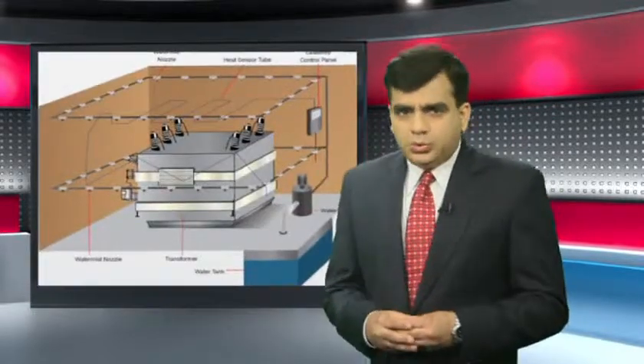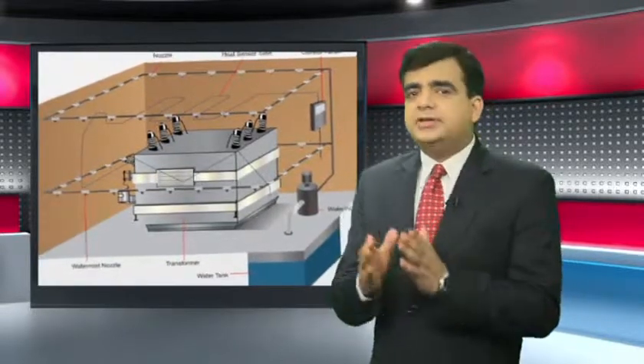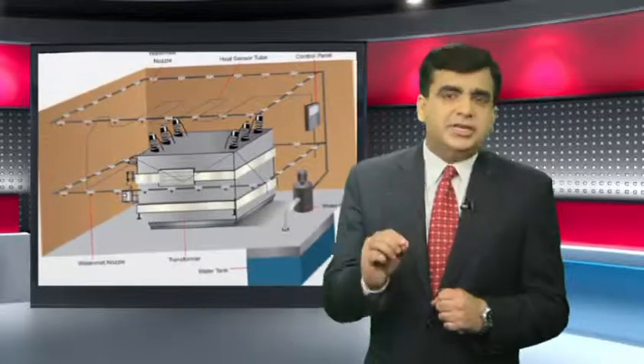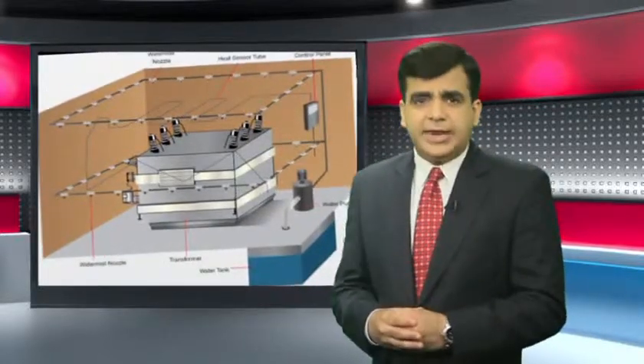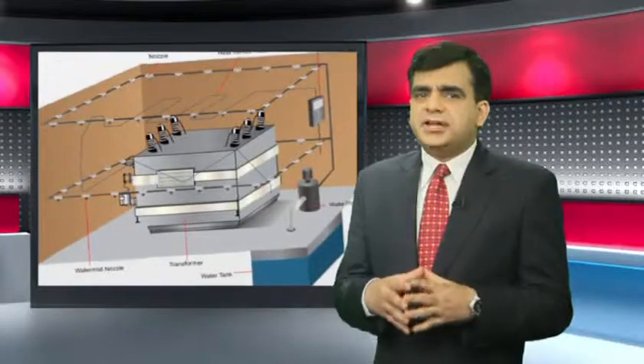The transformer Auto-Quell system has been set up according to a design provided by the Ceasefire Design Cell, which studies the needs and vulnerabilities of the area at length. Do keep in mind that the setup may differ as per variations of applications. Okay, now let's look at the system. The first component here are the detectors. This system includes either smoke detectors, heat detectors, and rate of rise detectors, or a combination of these. It could also feature a linear heat detection system.